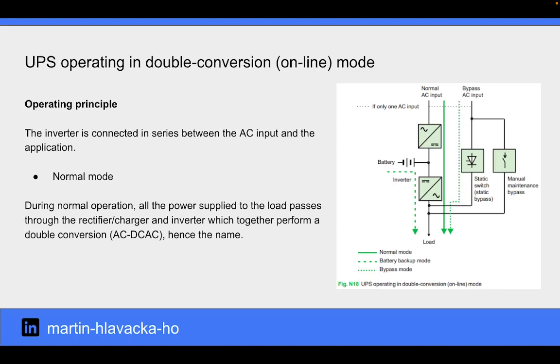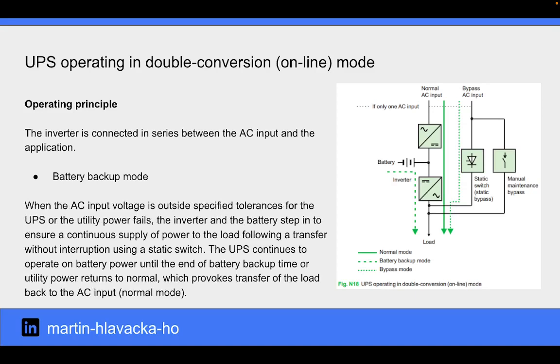A UPS operating in double conversion mode has the inverter connected in series between the AC input and the application. In normal mode, all the power supply to the load passes through the rectifier and inverter, which together perform a double conversion. In battery backup mode, the inverter and the battery step in to ensure a continuous supply of power to the load following the transfer without interruption using a static switch.